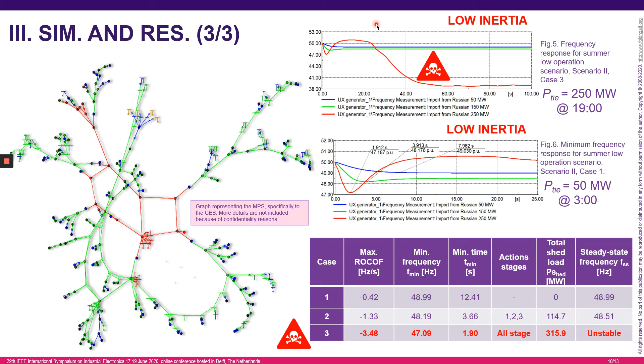If you look over here, the simulation results for case number 3, that is an importation of 250 megawatts from Russia to Mongolia, you can see in red color over here that we have a frequency instability, okay? As you can see, at the very beginning of the event the frequency tried to recover, but at the end, around 35 seconds after the disturbance, the system does not have enough power to keep the balance, and as a consequence, the system is unstable, okay?